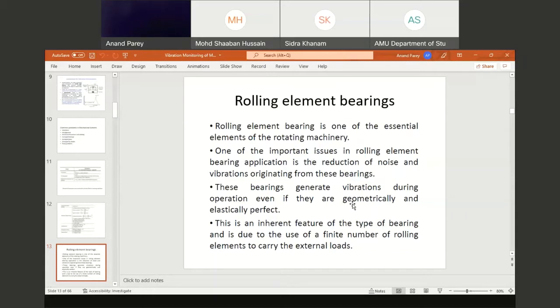There is sometimes a misconception that if there is a good bearing or good gear, then you will not find that particular gear mesh frequency or outer race frequency. No, it is always there, because it depends on the configuration of the bearing and the gears.